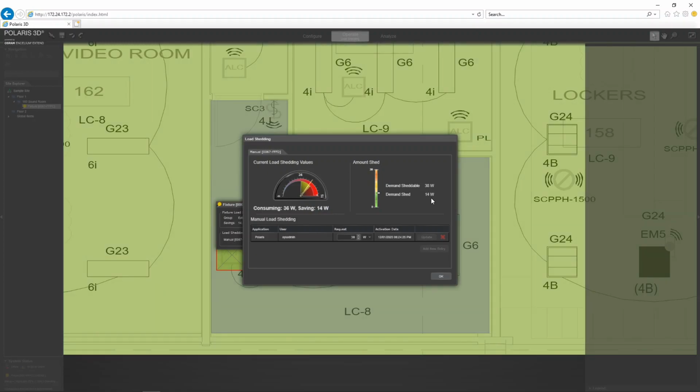Consumption is reducing. It won't go fully to the 0 of the consumption because the difference between that 50 watt and the 38 watts is the power needed to power the electronics of the driver and the fixture, to have it do its thing. So you won't have the exact 50 watts available. In this case, we had 38 watts available.